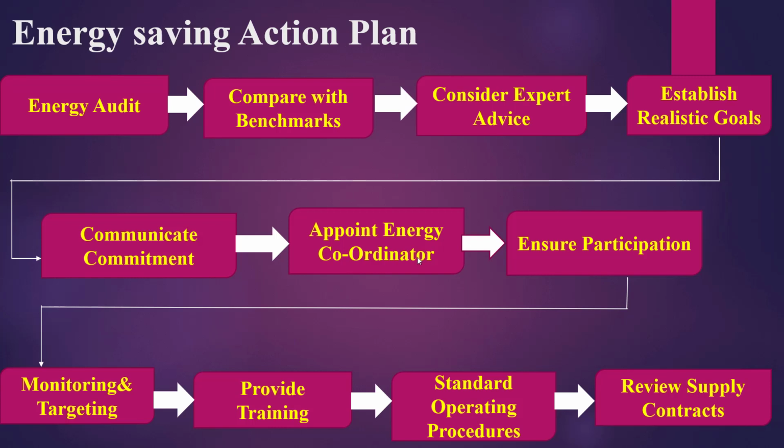In a hotel chain or group, targets may be set by reference to the best performer, or more realistically, the worst performers may be compared with the average. Where industry norms are available, these may be used as target values. See, for example, the tables for guest rooms, kitchen, and laundry. An alternative, but less common, way to set targets is to develop them with reference to theoretical calculations, such as how much heat the building gains and loses, or how much electricity is required for the lighting system to achieve a given level of illumination.